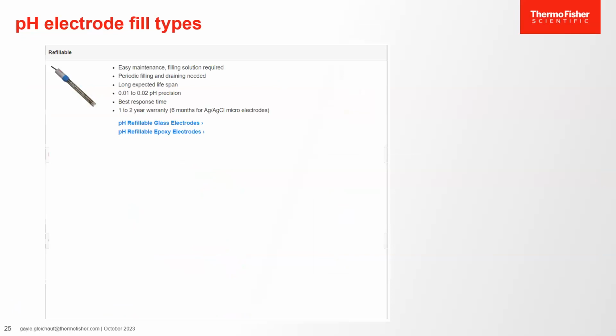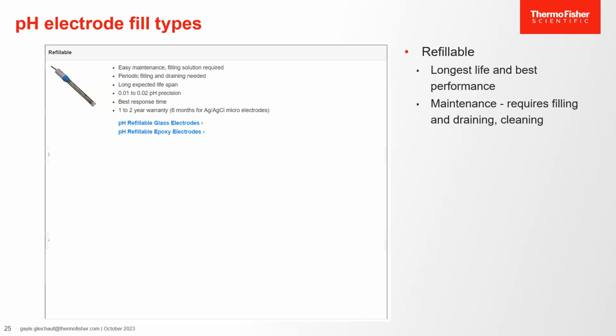All pH electrodes have a reference electrode fill solution. Some are refillable. Others are sealed and are low maintenance. No topping up, draining, or refilling needed. In general, refillable electrodes tend to make the best electrical contact between the reference and the sample. Because the fill solution can be drained and refilled, it's possible to restore performance to a refillable electrode with timely maintenance. These have the longest life and the best performance overall.